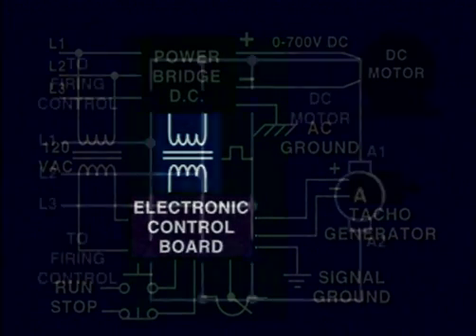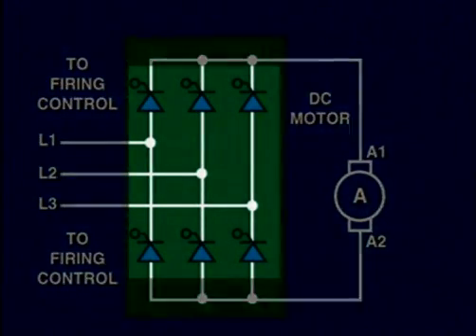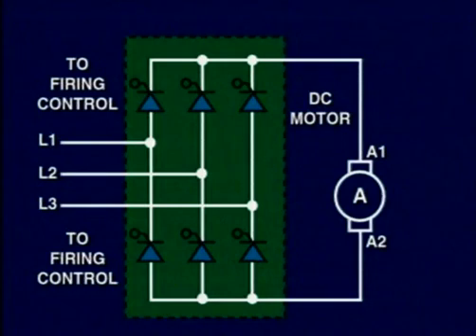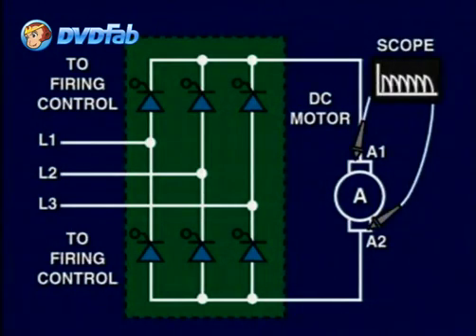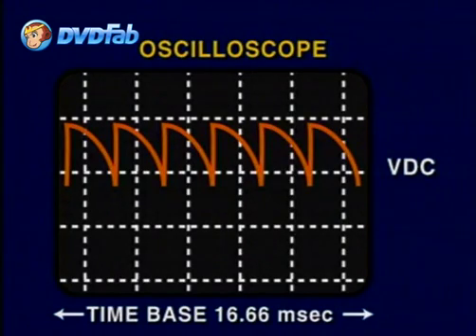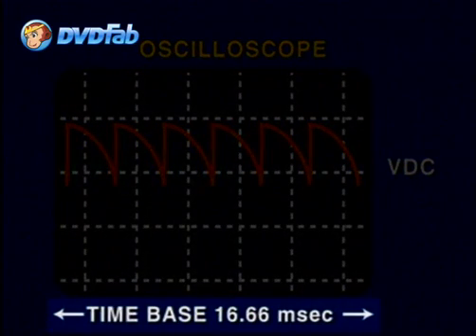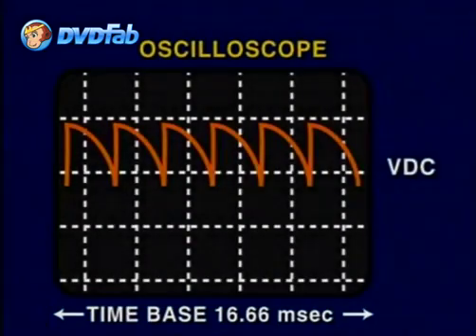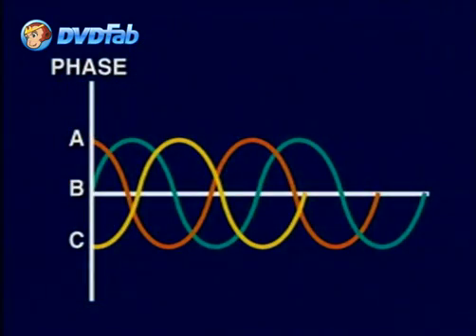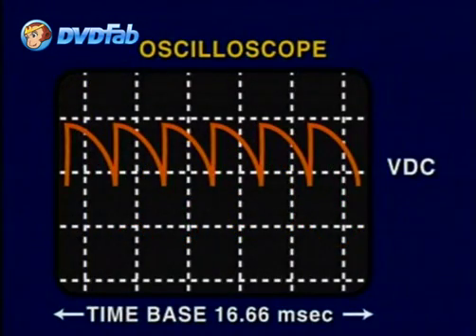If a problem is suspected with the drive, in this case one which uses a so-called 6-pulse bridge, the first thing to do is to check for proper operation of the SCRs, making sure they are firing and providing power to the motor. To do this, you can place an oscilloscope across the A1 and A2 terminals of the motor or from the terminal coming from the power bridge. You should observe this type of curve, where all 6 SCR curves should be present within a 16.66 millisecond range, which equates to 1 pulse for each SCR on each half-cycle of the 3 phases. Make sure the scope is set for at least a 16.66 millisecond scale. All 6 pulses must be present.